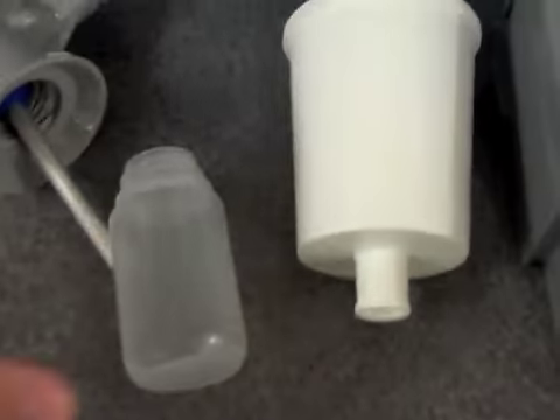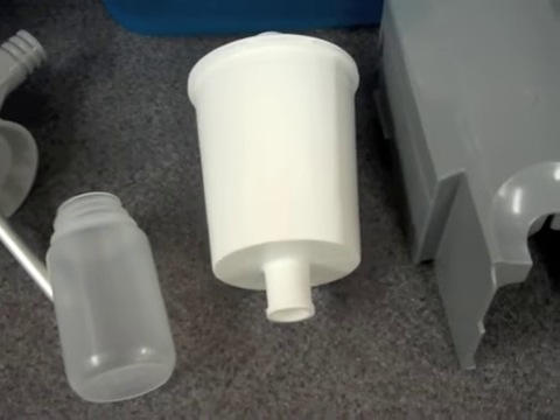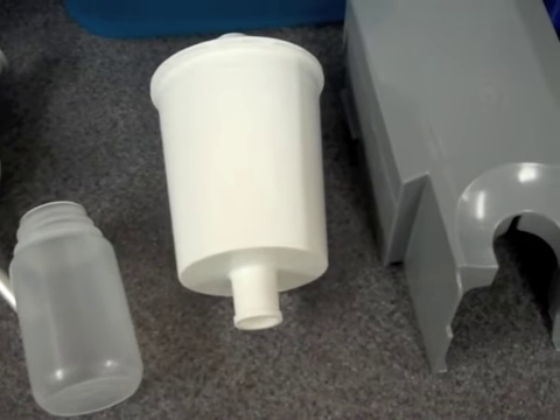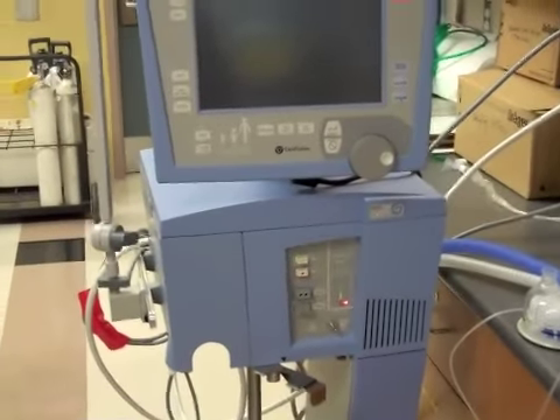The first thing you're going to do is collect all of your equipment. So you can see here I've got my various pieces of equipment for my expiratory filter and housing. I've got a double limb heated circuit here with an inspiratory filter and a humidifier pot. And the first thing I'm going to do is put that all together, install it, and then do the check.